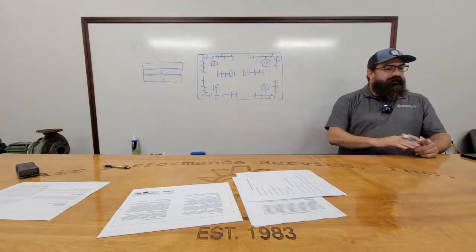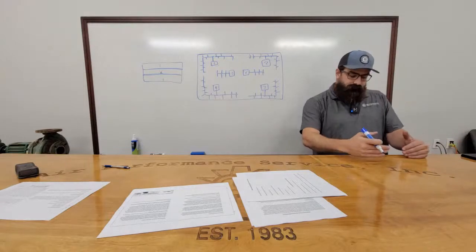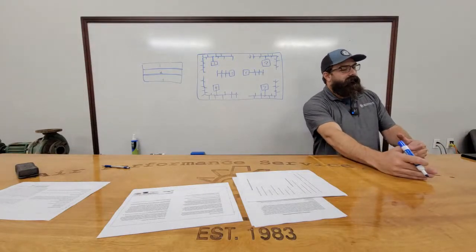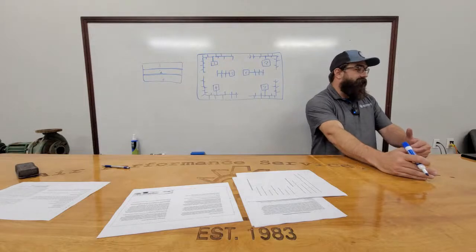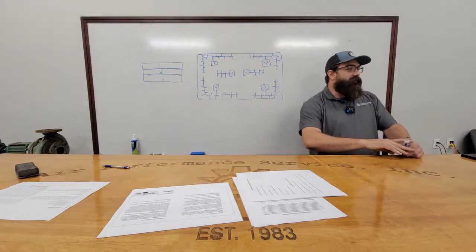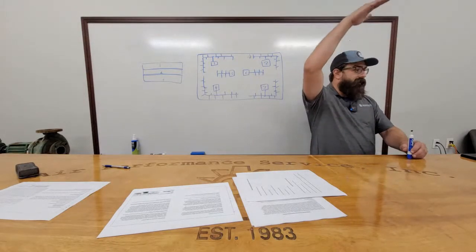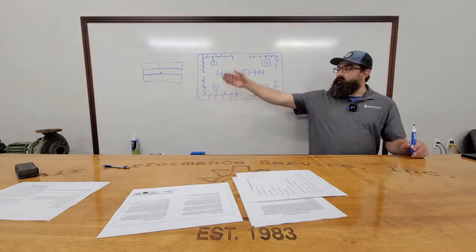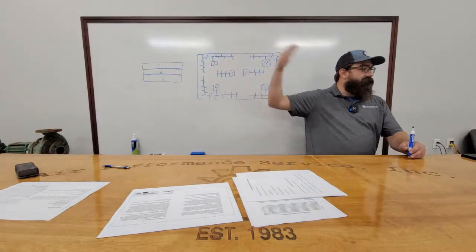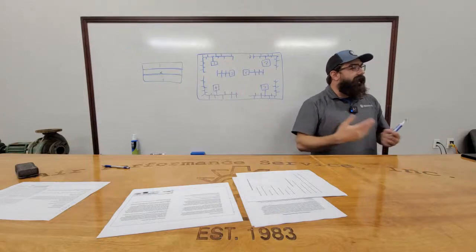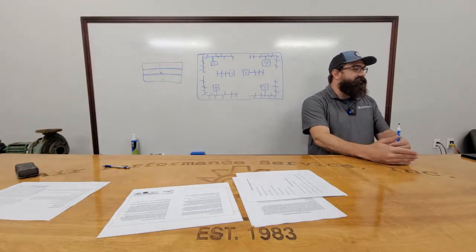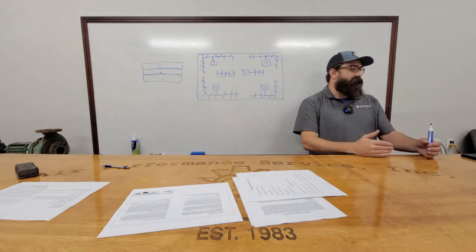In others, let's just say we have a six-story building with a bunch of VAV air handlers and fan power boxes, okay? Same thing. We would stage each floor independently. You're not going to bring all six on at once. You would start the same way. Typically, we're going to start with the hot floor in the summer, the cold floor in the winter. Not all buildings are set up that way, but if we have the time and the customer requested it and paid for it, then we can put those algorithms in place.